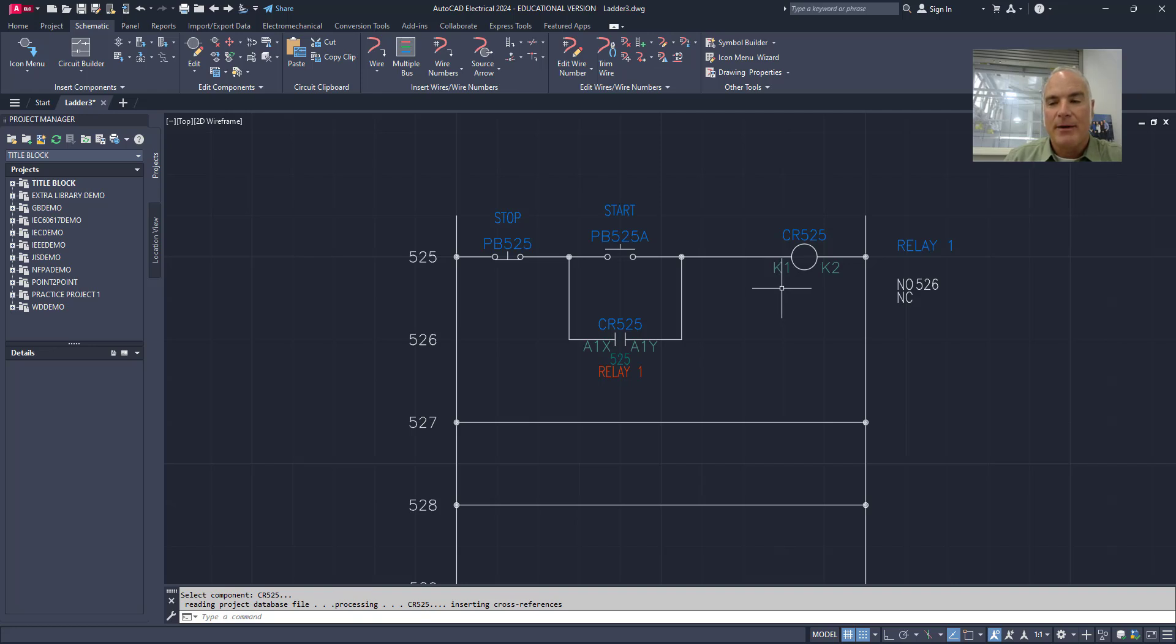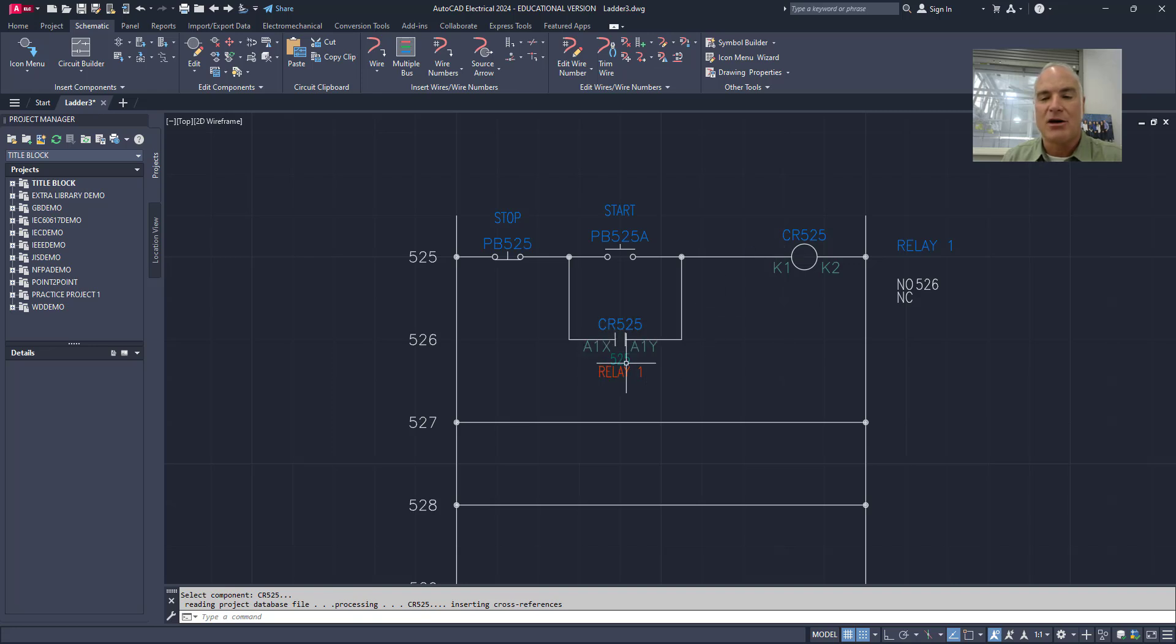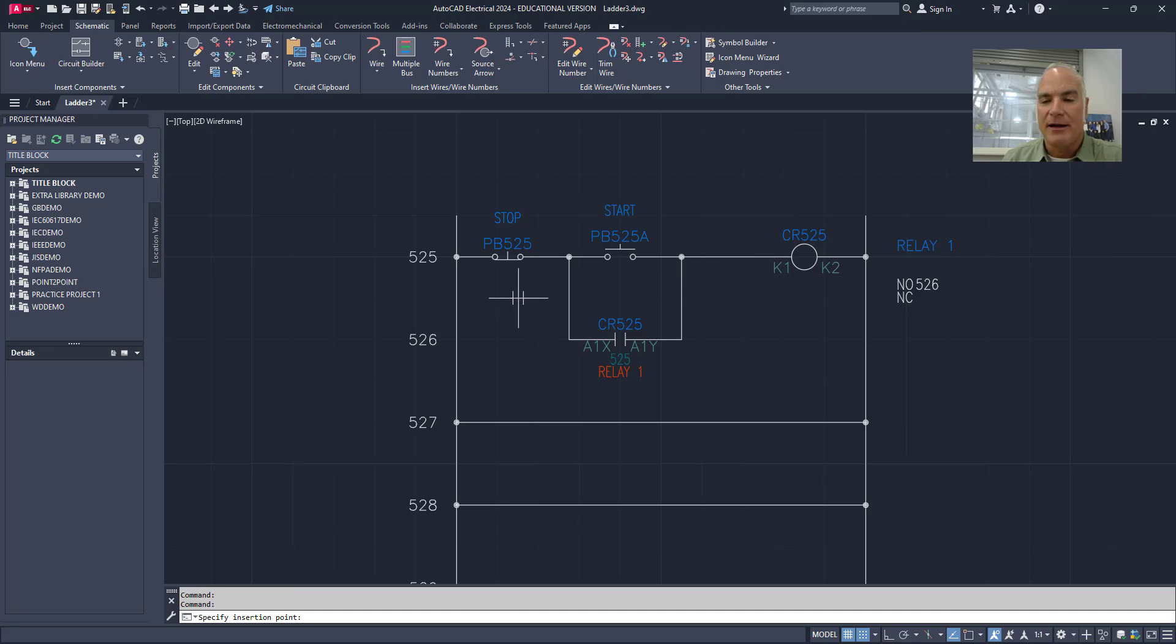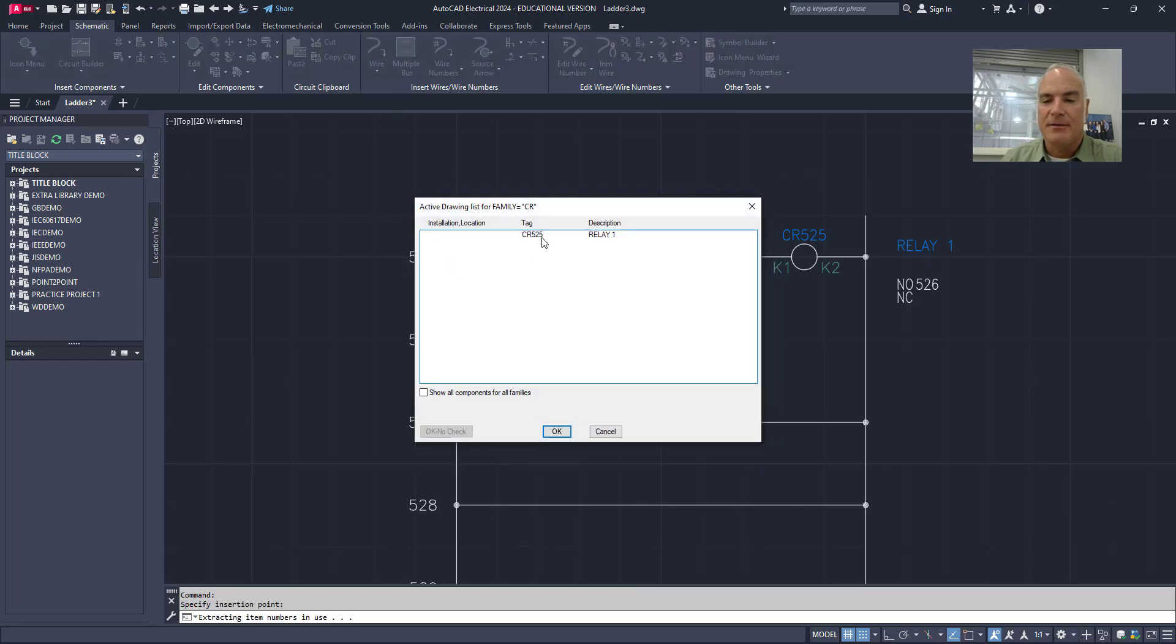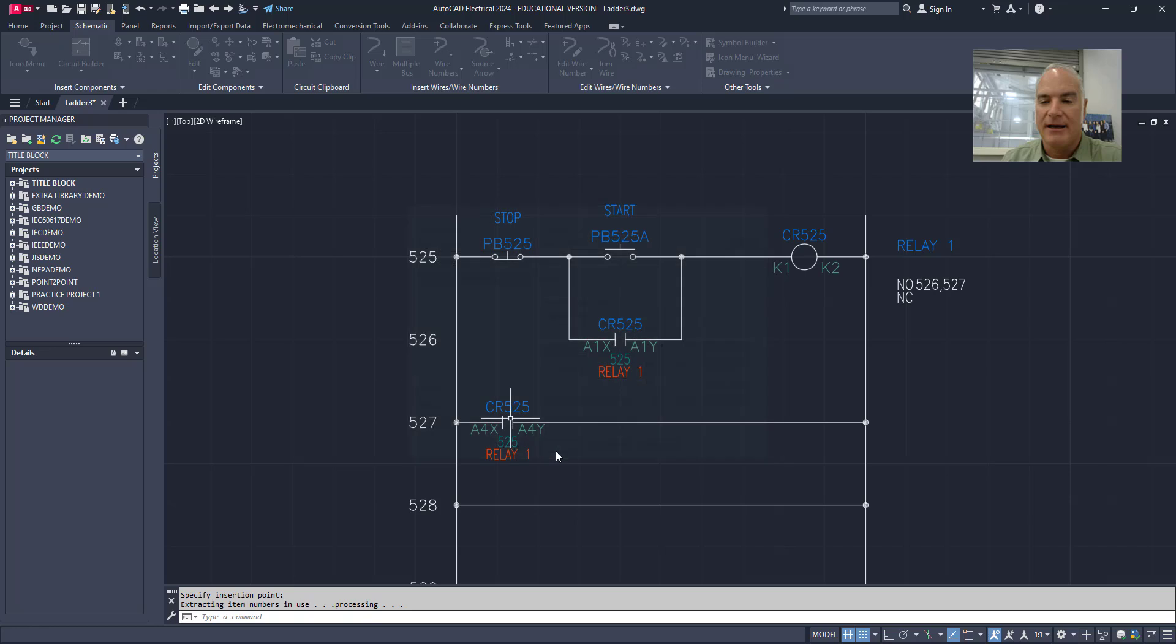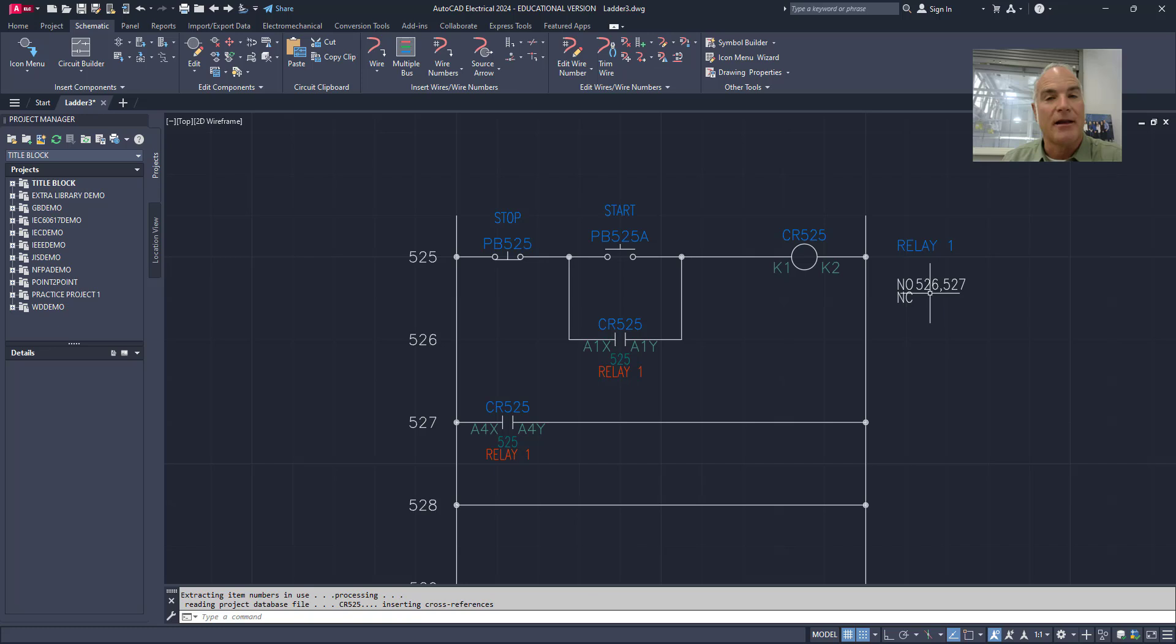Notice that, by the way, it does put in connections. So for your relays, K1 and K2 are normal. And this is A1X and A1Y. Now on this row, I'm going to put another normally open contact. And you'll notice because of the relay that I've chosen, it's going to put in different contacts here. So I'll go back again to my component menu. I'm going to use this normally open component and I'm going to put it down here on 527. Again, I will say I want it to be linked to that original relay right there on 525. Say OK. And just OK again. And notice now that I've got different contacts. Then this one. It also adds those contacts over here. So this relay is controlling contacts on line 526 and 527.